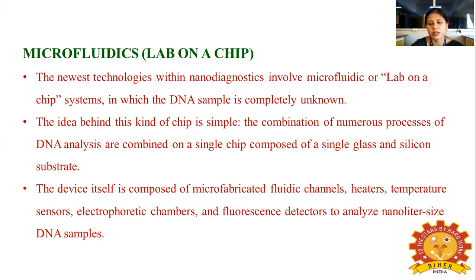The device itself is composed of microfabricated fluidic channels, heaters, temperature sensors, electrophoretic chambers, and a fluorescence detector to analyze nanoliter-size DNA samples. These devices are described as capable of measuring aqueous reagent and DNA solutions, mixing the solutions together, amplifying or digesting the DNA to form discrete products, and then separating and detecting those products. Using a pipette, a small DNA-containing solution is placed on the fluid entry port and a reagent-containing solution on the other port. Capillary action draws both solutions into the device, but hydrophobic patches positioned just beyond the vent line in each injection channel stop the samples.